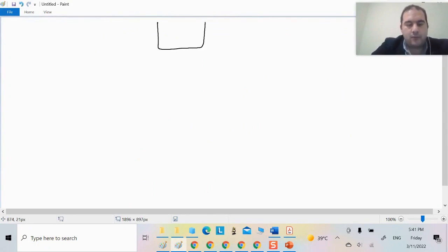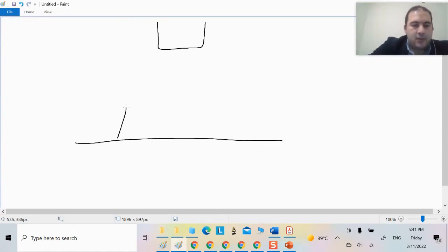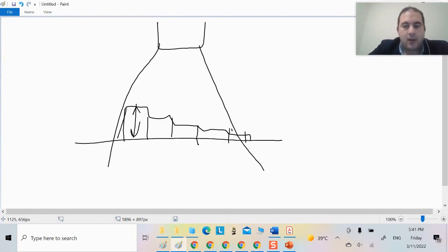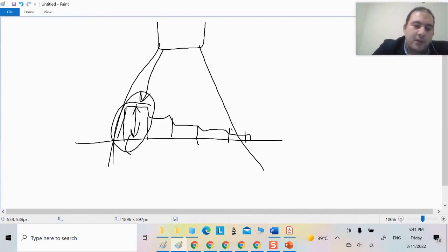I have an X-ray tube and I have the film. This film uses something that consists of blocks like this, but with different thicknesses. Here, the thickness is large, and then it decreases gradually along the length of my film, and it starts to be exposed to X-rays, right? So, normally, the part that has higher thickness will absorb a lot of radiation, meaning the transmitted photons that reach the film itself will be fewer, right?